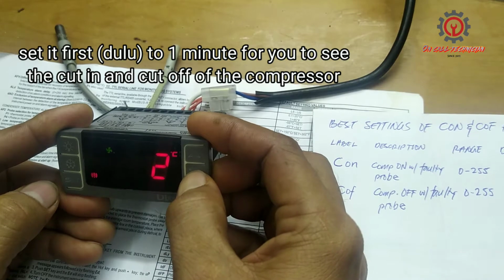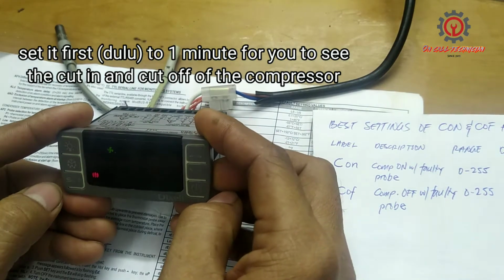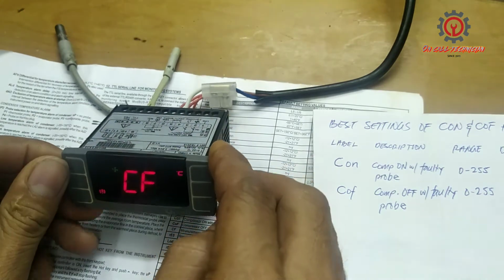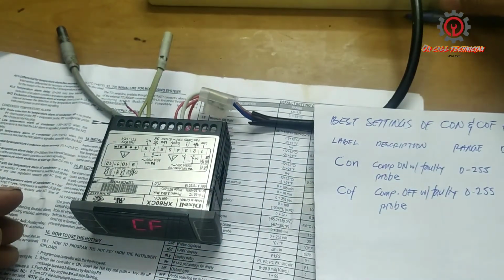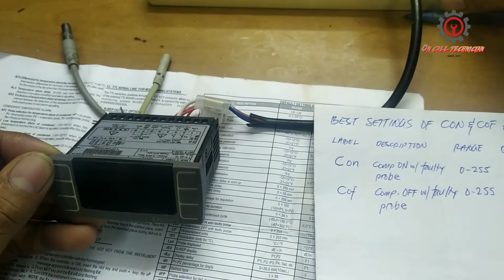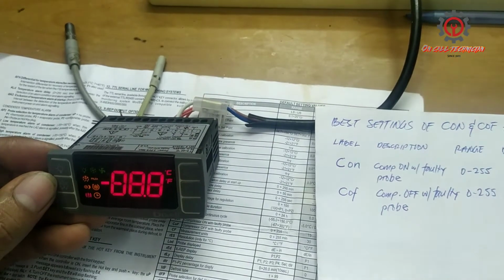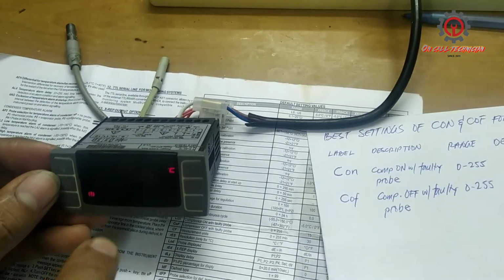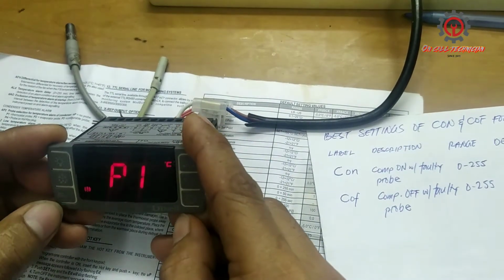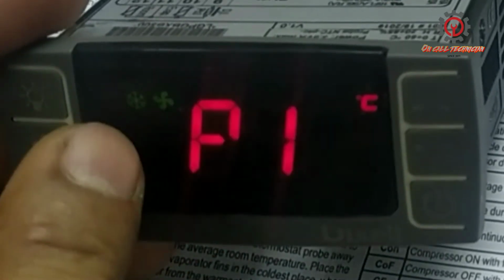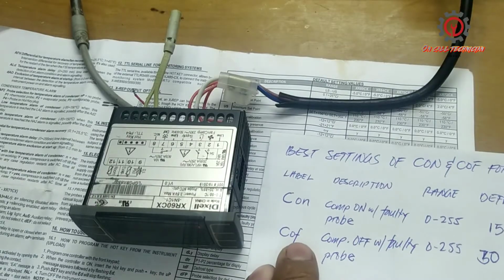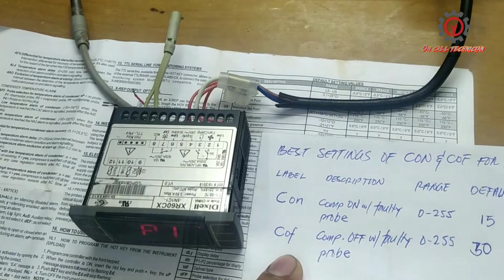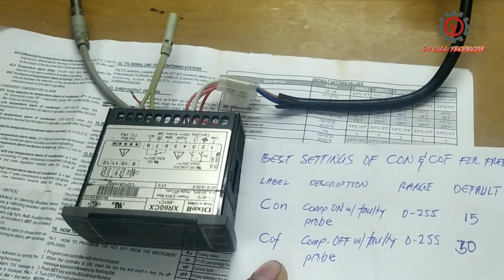And let's find out what happened. Set, and I'm going to reset this. Off, on. Okay, we got the P1 alarm. I'm going to silent that one. Now you see, compressor is on, and let's wait for 1 minute, and let's see if the compressor off will engage, because I set that first to 1 minute.